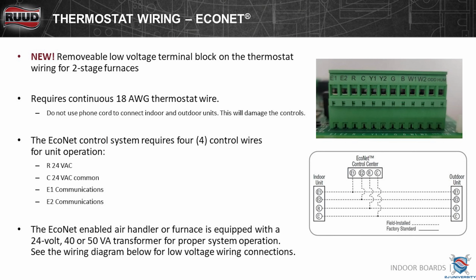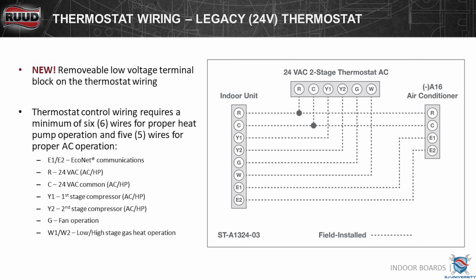Same thing with the furnace board, still 4-wire connectivity when you're going Econet. You've got E1, E2, R, and C all the way through. 24 volt legacy, when you're wiring 24 volt legacy, once again, you can wire from your thermostat to your furnace with 24 volts. And if you're using base tier stuff, you're still 24 volts to the outside. But as soon as you go 15 SEER AC, 16 SEER AC, and 16 SEER heat pump, it's 4-wire connectivity outdoor to indoor.